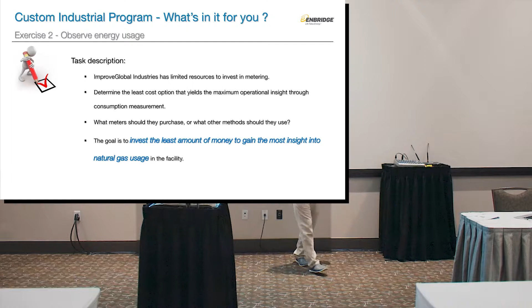If somebody didn't catch this, what was being referred to is that because of the ratio of process load versus seasonal load, the process load is obviously much higher. So the idea is to focus on the steam boiler, put a meter there, and then subtract that from the facility meter to get the rest. That's a perfect solution. The only caveat is I'd ask Enbridge to help get a read of this meter into my DCS system in the facility, so I don't have to wait for monthly data. I can get hourly or daily data, whatever I want.